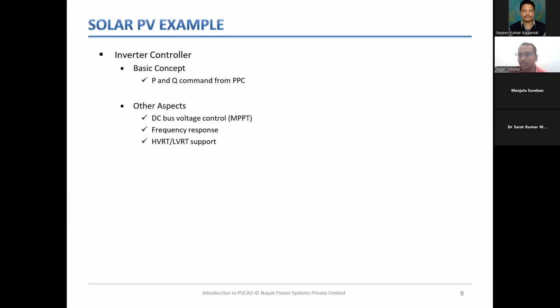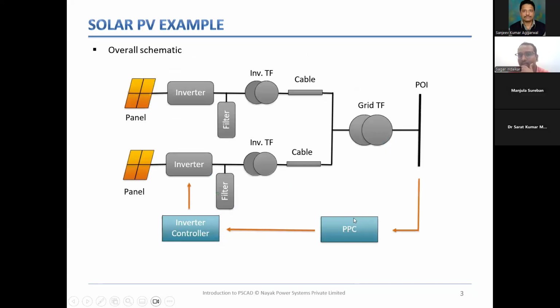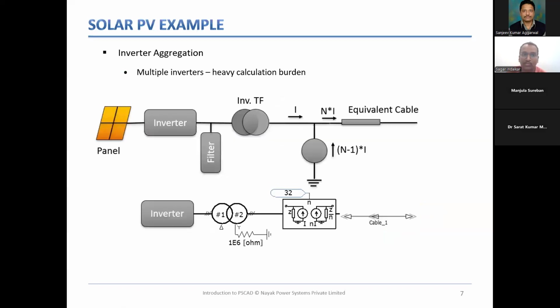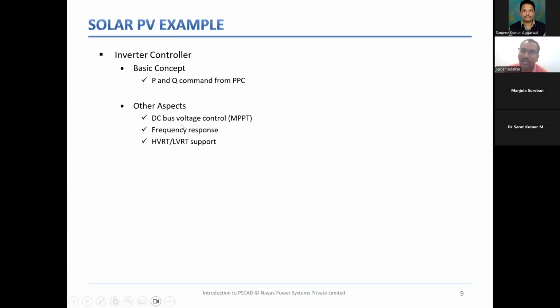Now, why is the inverter control faster? Because the inverter controller is actually part of your power supply. For example, if you go back here, you see the PPC is receiving measurements from the grid. This is a digital measurement, and then it is giving orders. So this portion is a digital communication based device. It does not have any power circuit, whereas an inverter is actually generating that power. It is close to the power circuit, so it is able to take decisions very fast compared to the power plant controller.